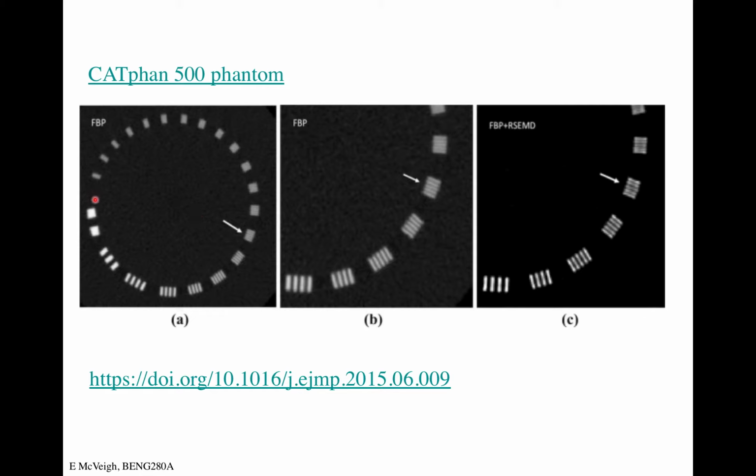So here we see basically a pattern of these lines, and they have cycles per centimeter, cycles per millimeter, and you just basically look around and make plots and see when the contrast drops down to 0. That's one way of measuring spatial resolution. And you can see that they're all at the same radius, and the spatial resolution we're testing here is the resolution with respect to changing theta, right? We don't have it as a bar and looking basically as a function of r from the origin. It's theta as we're going out here.